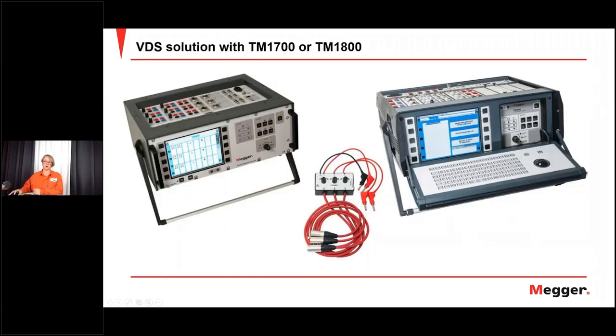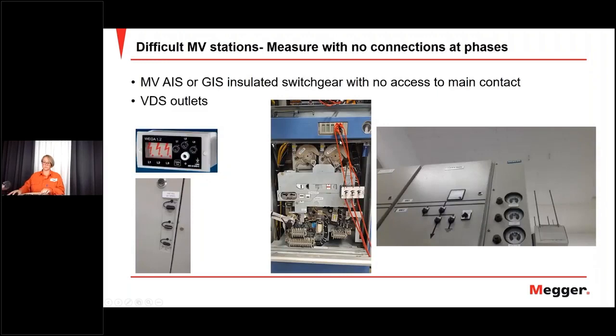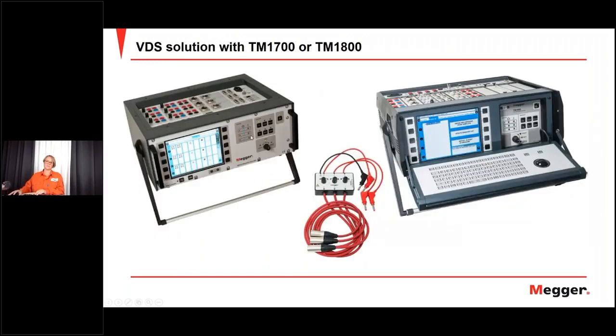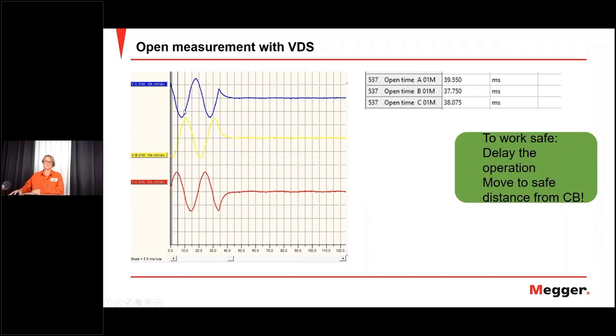You work with this little box, you see it here in use, and the analyzer, either TM1700 or 1800. You get here an opening and you see an interruption, and you get it also in a parameter list. So you get it like listed results. But again, when you do this kind of measurements, I recommend to delay the operation and take a step maybe into the other room or on the other side of the transformer or something. Move away from the circuit breaker because this is live operations, live changes in the circuit breaker.